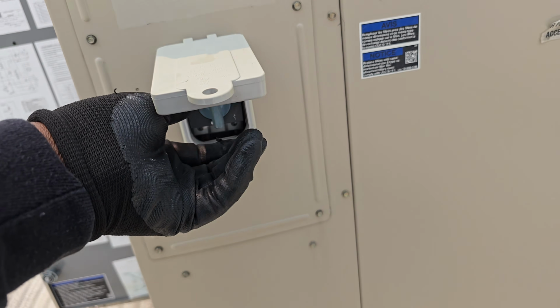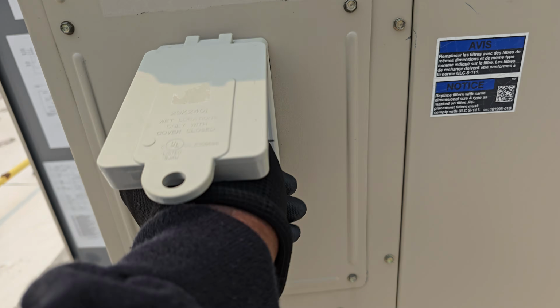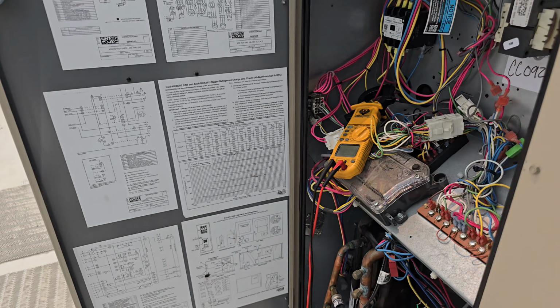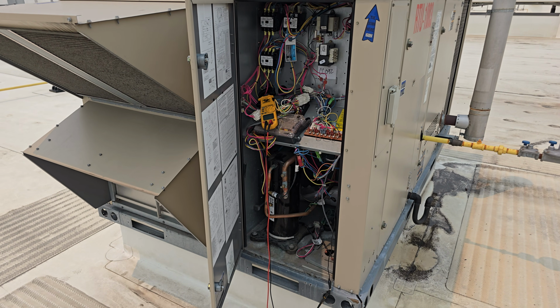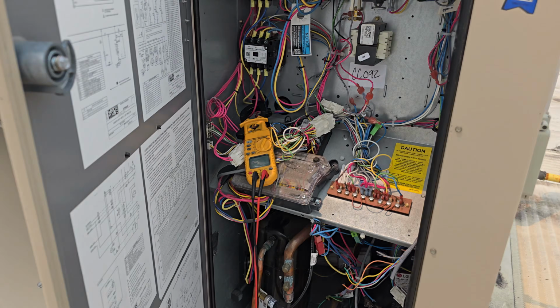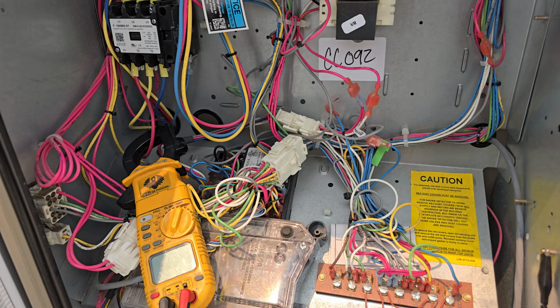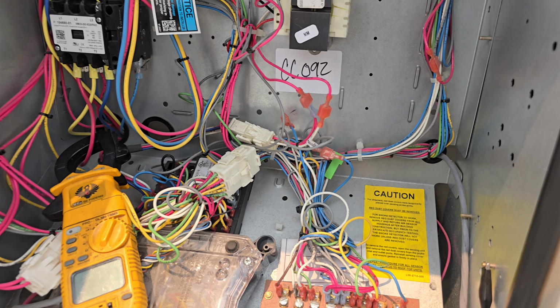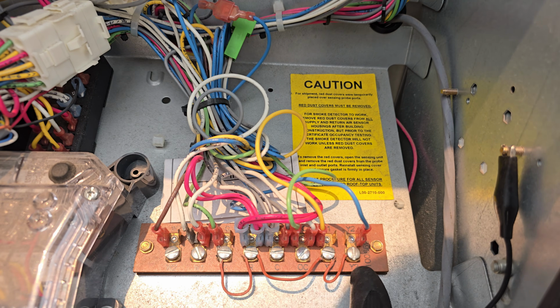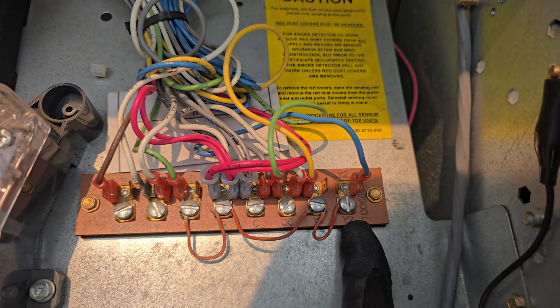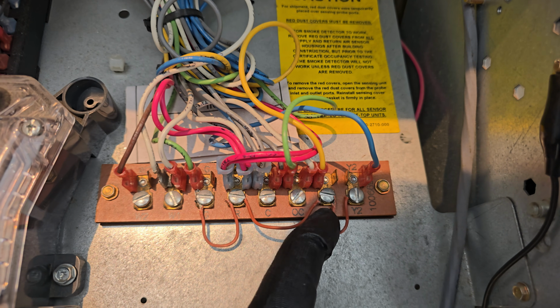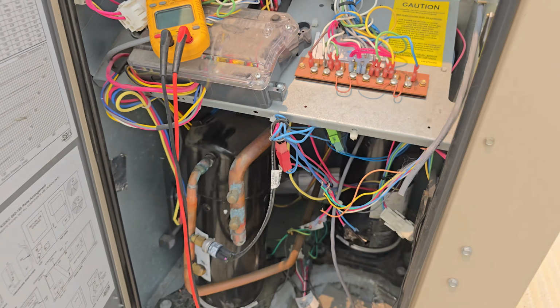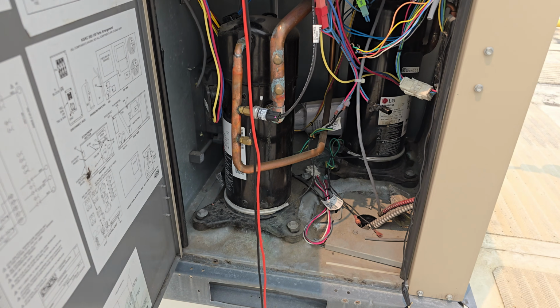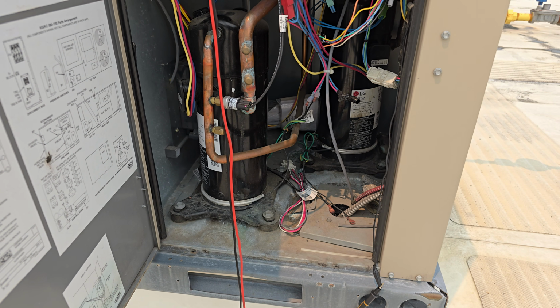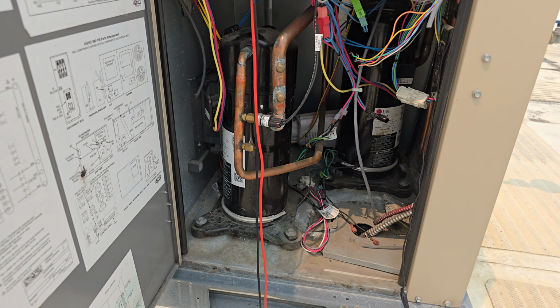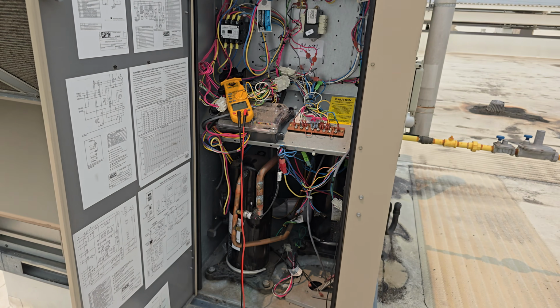So I'm going to turn it off. Please remember to always turn it off. So my thermostat is eliminated as not a problem. The next thing I will do is disconnect my Y2 and bring in my Y1. Sometimes you may want to check, oh, you think the compressor is not the problem? I don't know yet, but I think the problem is coming from the low voltage side.